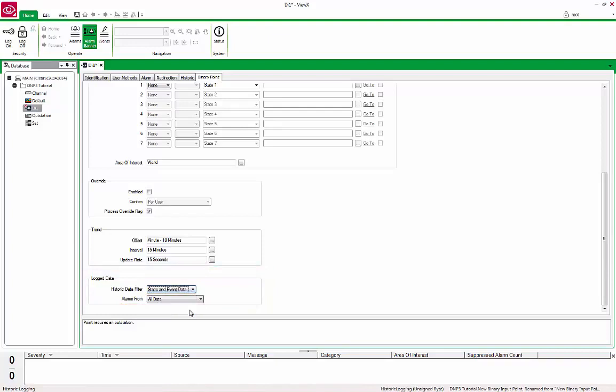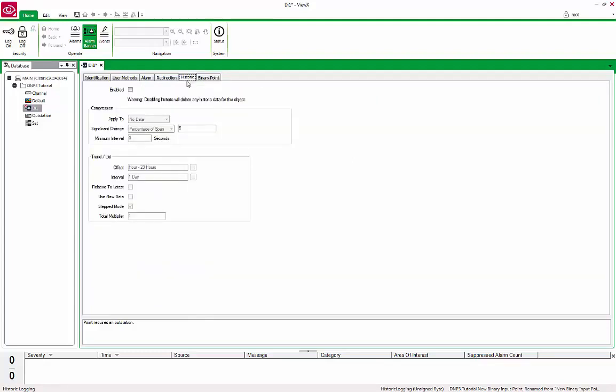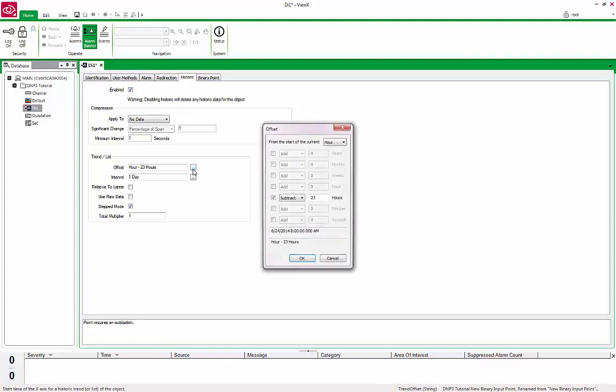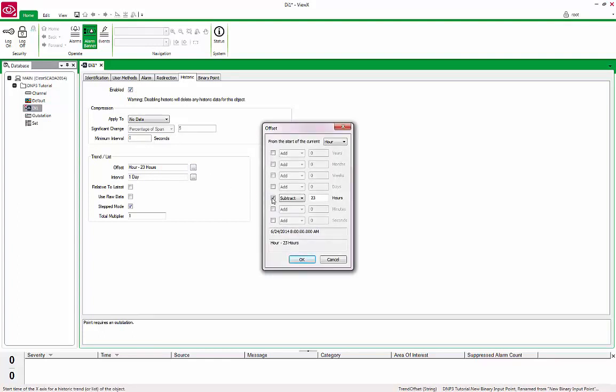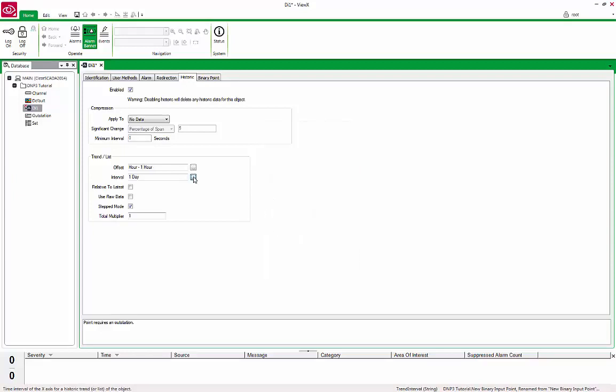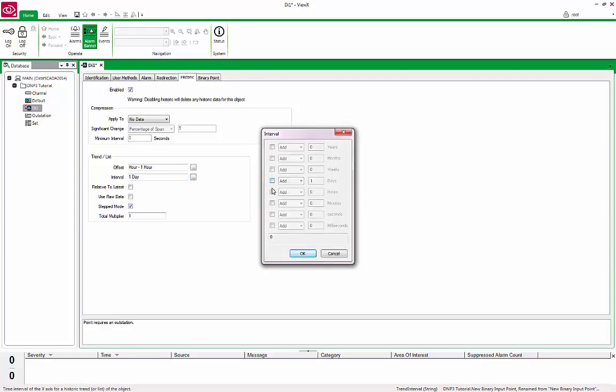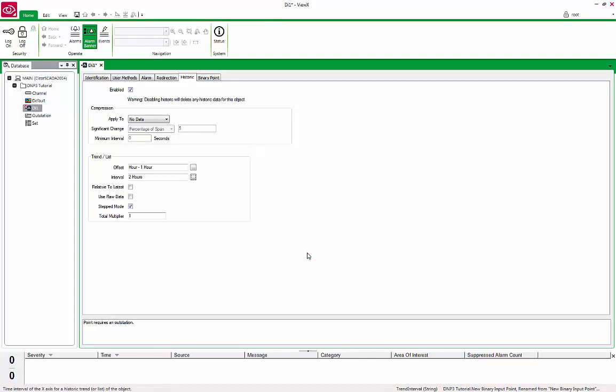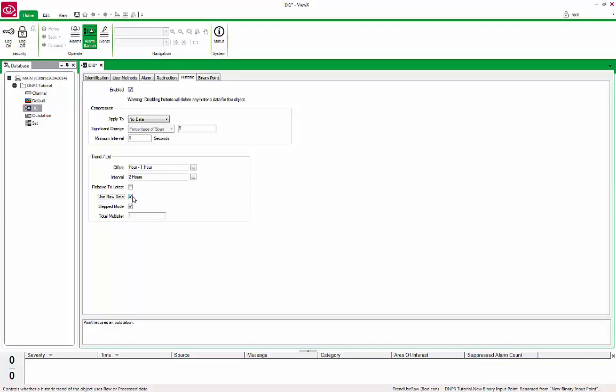This will allow all informational data to be stored in ClearSCADA as history. Click on the Historic tab and check the Enabled box. Under the Trend List section below, set the Offset to H-1H and the Interval to 2H. This will default the Trend Time Span to start from the beginning of the last hour with a span of 2 hours. Finally, check the Use Raw Data box at the bottom. This tells ClearSCADA to display trends using the raw samples rather than processing the data prior to sending it to the client. Save and close the form.